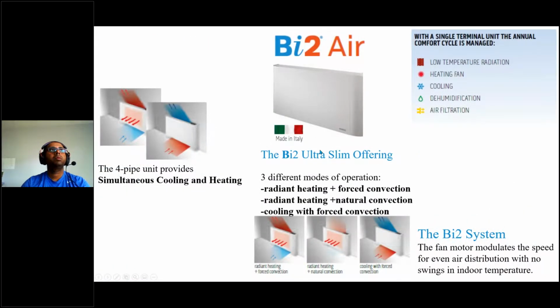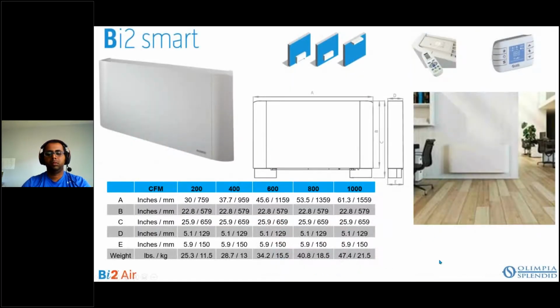And again, it's ultra slim. You have low temperature radiation, heating, cooling, dehumidification. So this could be a two-pipe system for hot water or a two-pipe system for chilled water, or you can have both the hot water and chilled water coil in the unit, and now you have the ability to very effectively dehumidify. So if you have a boiler and a chiller in this building, you're set up with some very, very good opportunity to control that comfort in that space.